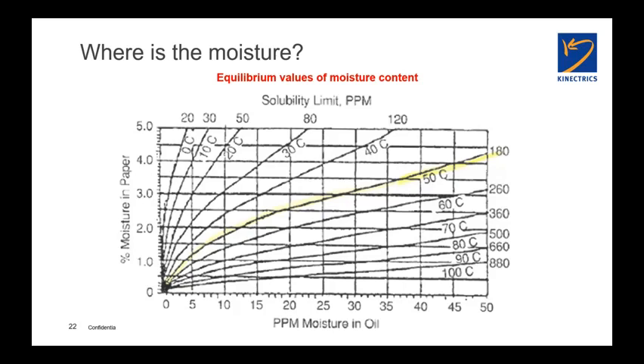All labs should be performing tests to a defined test standard, for example the ASTM D1533 Karl Fischer for moisture in oil, or the ASTM D1816 for dielectric breakdown, whatever. Those ASTM test standards have a paragraph at the end of them that talks about interoperator accuracy, reliability, bias, and things like that. Any reputable lab should be able to reproduce those results based on that test standard, and you should see very, very close results between labs.